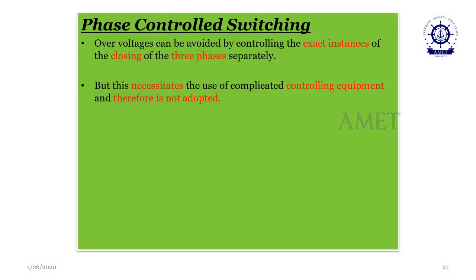The next method is the phase controlled operation of circuit breakers. From the name, it's very clear: phase controlled. Instead of closing all the phases at a time, we can close them one by one. First we control one phase at a time. By that way, the overvoltage is reduced or minimized greatly by the phase controlled operations with the proper sensors on each phase.